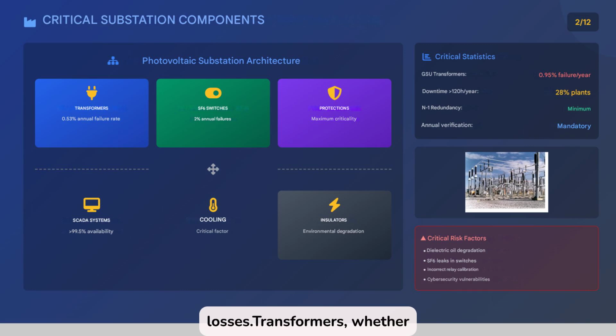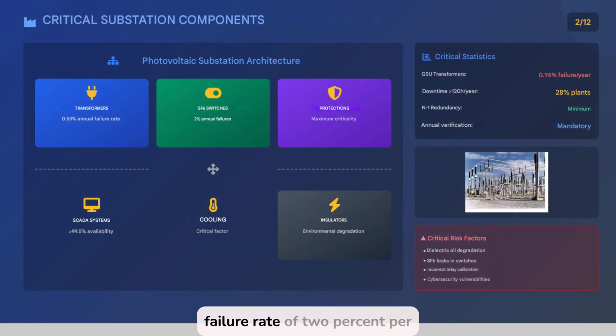Transformers, whether conventional or GSU, allow voltage to be increased to evacuate energy to the grid. Their failure rate can reach 0.95% annually, and 28% of plants experience more than 120 hours of downtime per year due to equipment failures. This implies lost production, revenue, and higher maintenance costs. Circuit breakers are also key. With a failure rate of 2% per year, frequent problems such as gas leaks or mechanical failures can spread breakdowns and affect other assets, with significant economic and operational consequences.